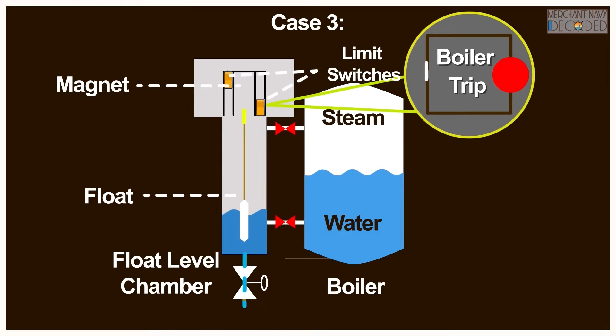Now in case 3, we are going to try out the boiler low water trip ourselves. In this, we shut the steam inlet valve to the low water level chamber. Then we shut the water inlet to the low water level chamber. Then we open the drain and empty the low water level chamber, due to which the float comes down and trips the boiler. This is carried out once every week.